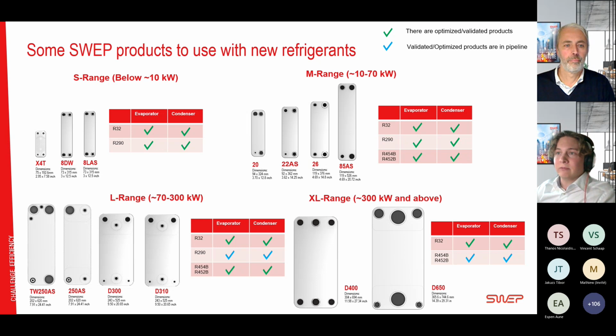And you can see that I have presented 3 different products here. So the X4T, a typical economizer that we would sell. We have the 8LAS, which is an asymmetric unit that can be used for condenser duties in smaller heat pumps. And then we also have the 8 double wall. That is a new product that we released quite recently. It's a double wall, so it can have a good fit with some propane systems if you want to ensure that you can have some safety included in the heat exchanger.